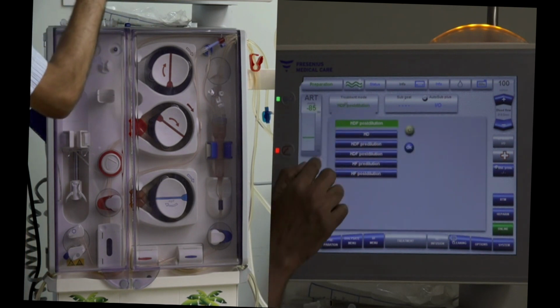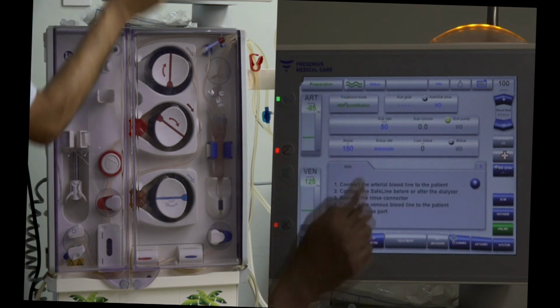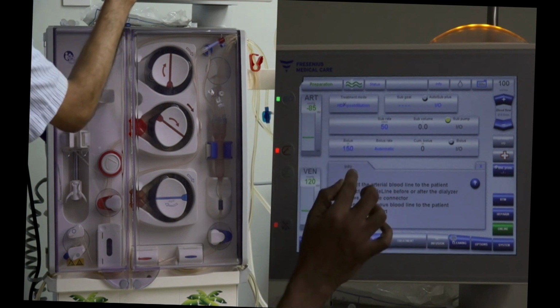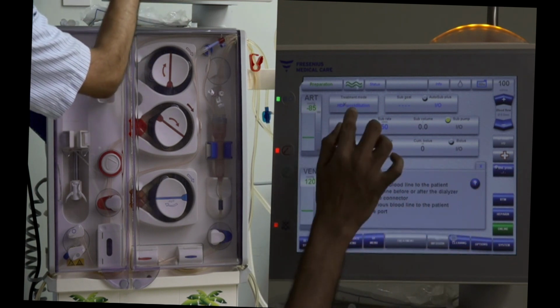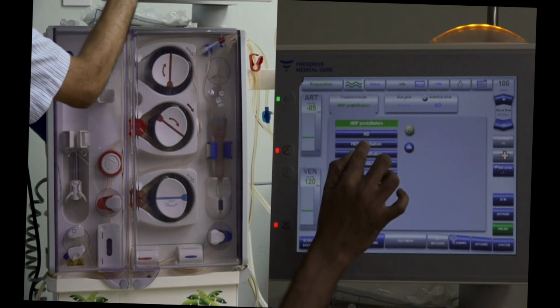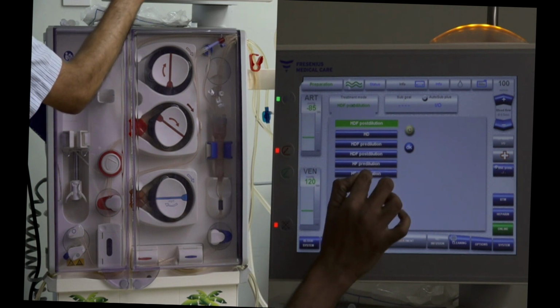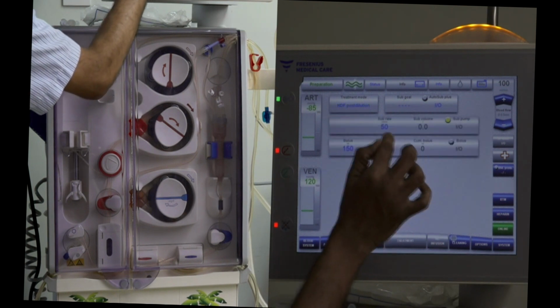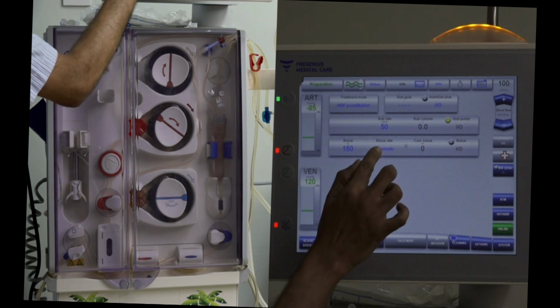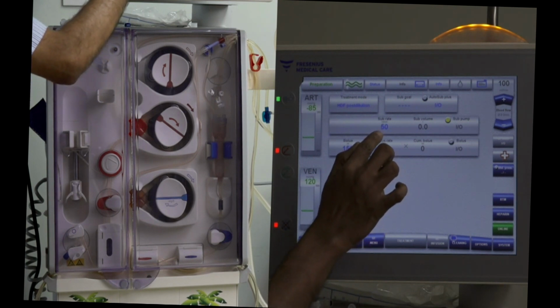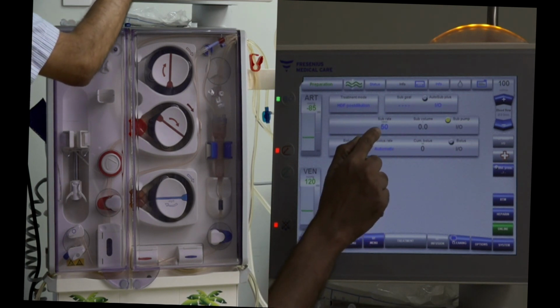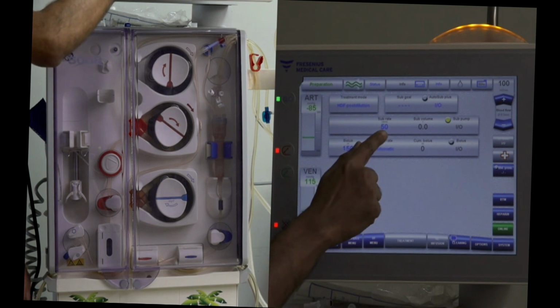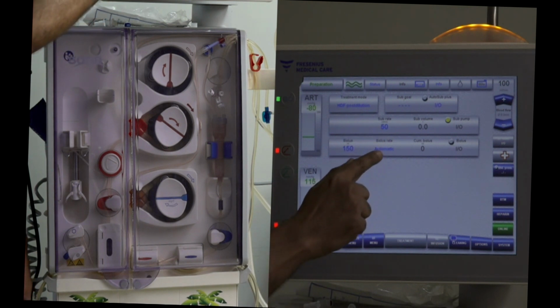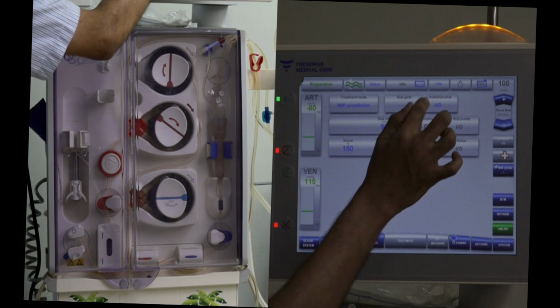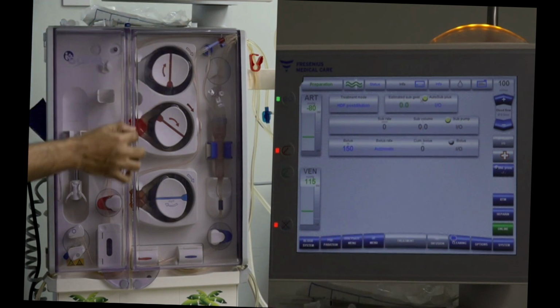The options for online are hemodiafiltration, post-dilution, pre-dilution, simple hemodialysis, or hemofiltration. So if I choose hemodiafiltration post, the default setting here is the last treatment I did, that is that the machine was delivering the substitution fluid at a rate of 50 ml per minute. However, the machine also has the auto sub plus function.